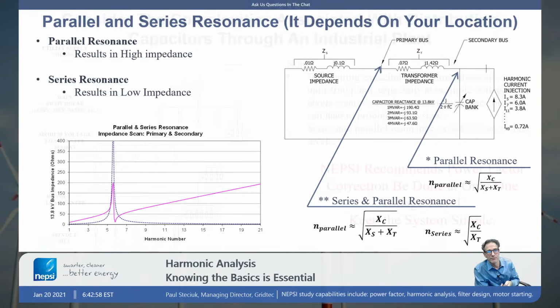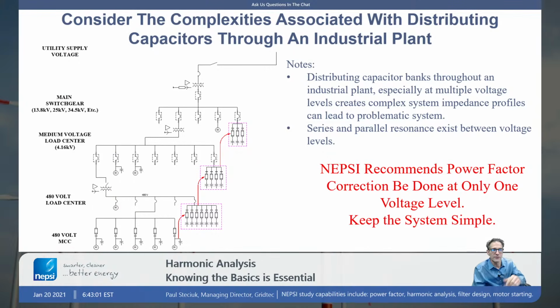So I bring this point up because oftentimes, especially in large mine projects or large industrial plants, there's a desire sometimes to put capacitors at each and every load level. So you might put capacitors at 480 volt, at 4160 volt, at the 13.8 kV level. Park the capacitors or the power factor correction as close to the load as you can. That's the concept that is often taught in school, because you then have a reduction in current, a reduction in kVA flow through your network. You have better voltage regulation through the network when you do that.